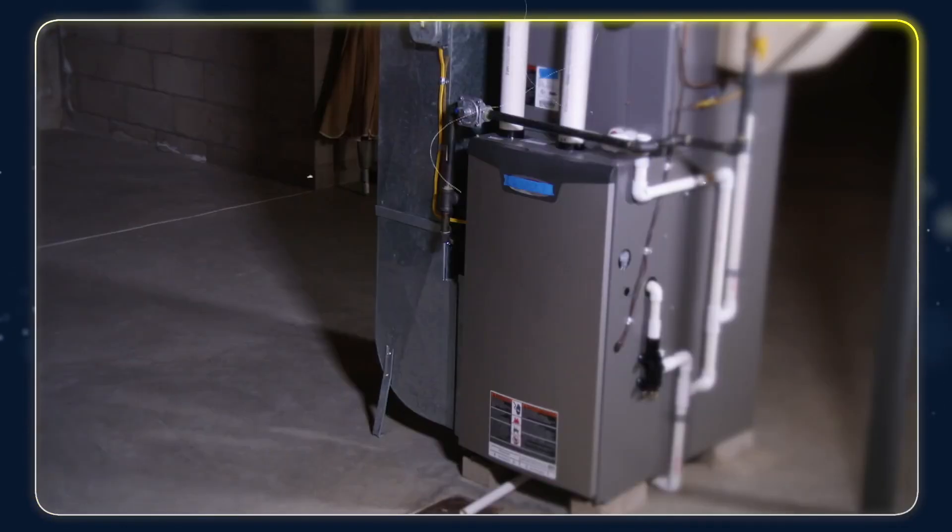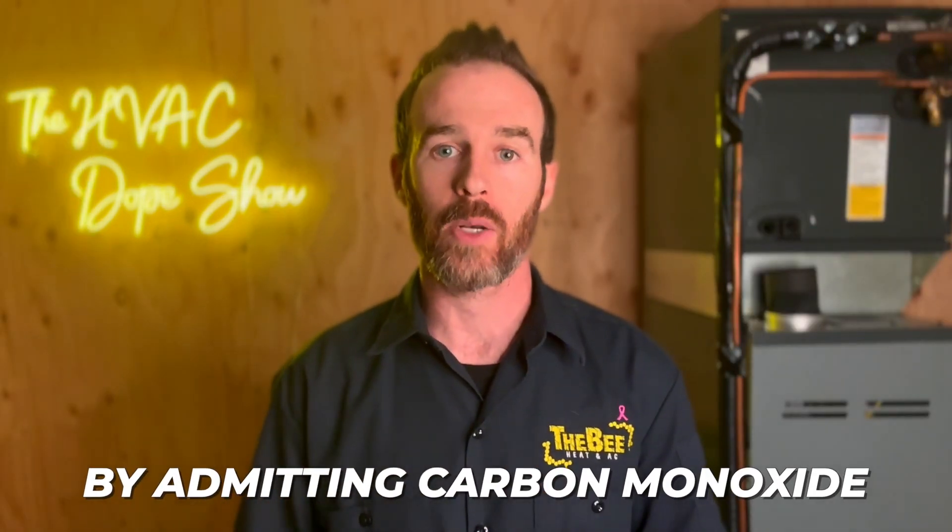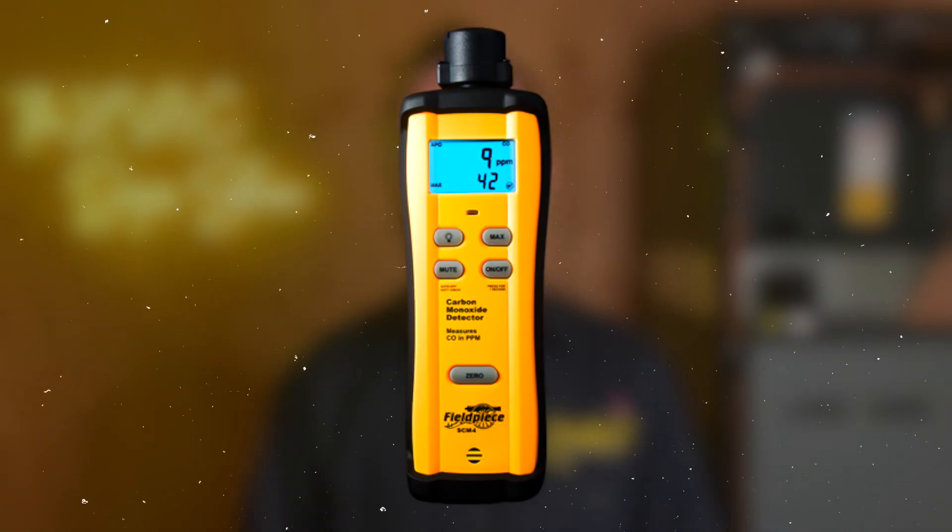The main reason I'm making this video — since it's a little different from our normal content — is because we are coming up on heating season and we are still running into a lot of these furnaces. The secondary heat exchangers that are hitting the 10-year mark or older are starting to fail, and they fail by typically plugging up or by emitting carbon monoxide, which we pick up with a CO meter.